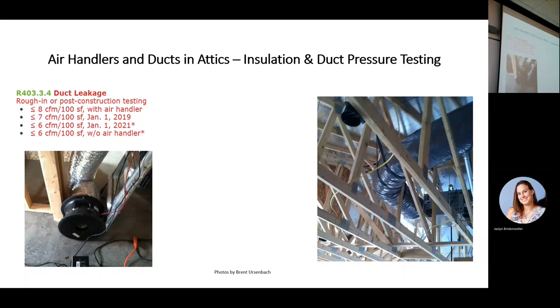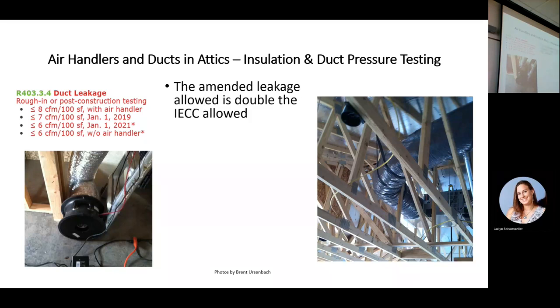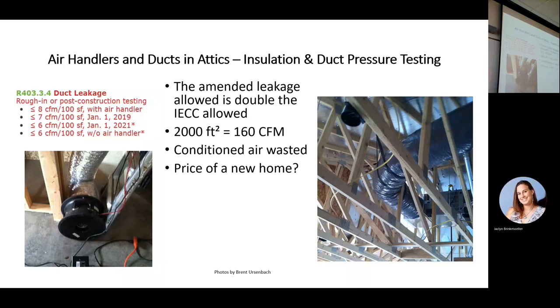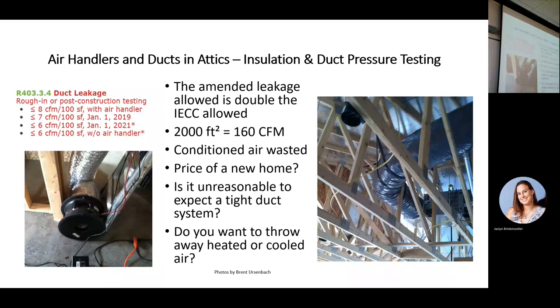Boy, these pictures just aren't coming through very good, but this was one we did in St. George. And they're doing some pressure testing at rough stage before there's any drywall. I need to fiddle with the contrast on those. The leakage requirement, as amended, if you have 2,000 square feet of conditioned space, you can leak 160 CFM. Now, do you really want to throw away 160 CFM of air that you just spent money to keep cool? I don't think I do.